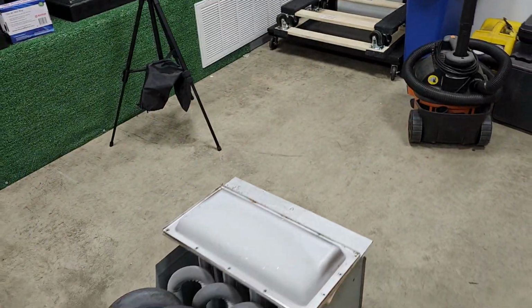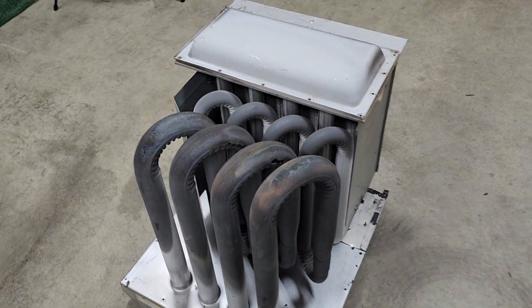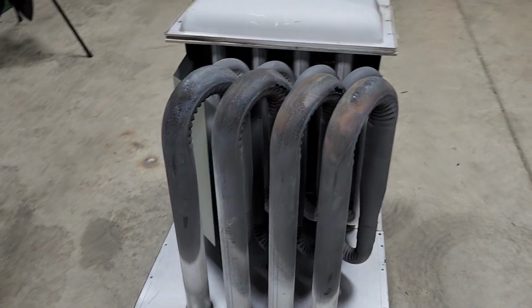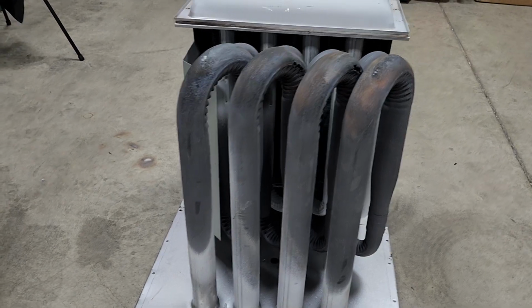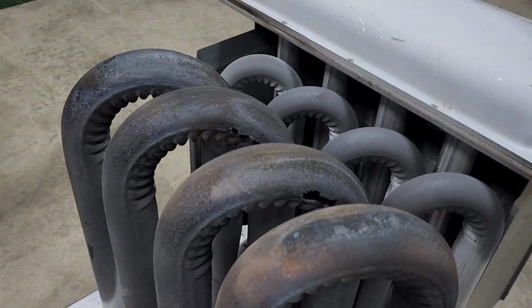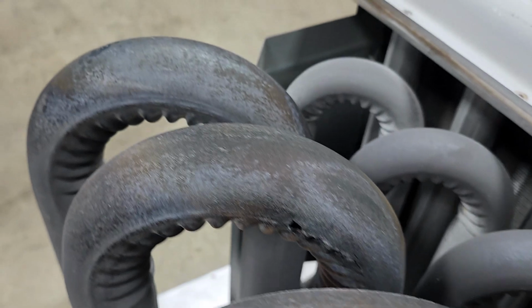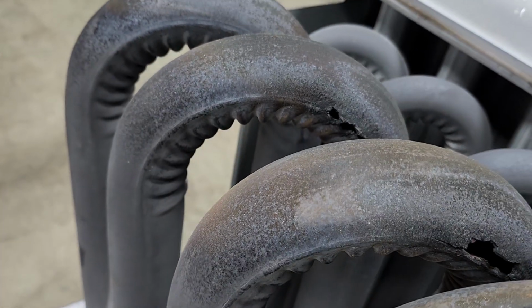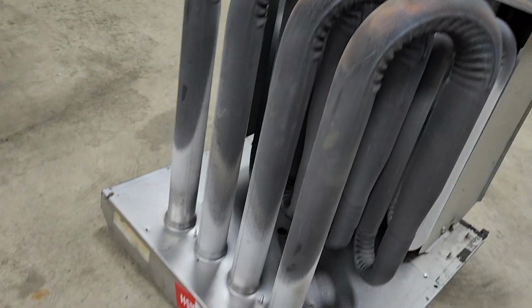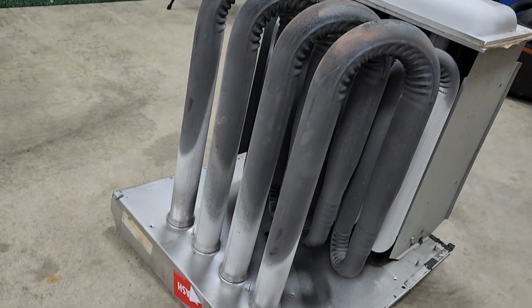I want to talk to you guys a little bit about heat exchanger failure, or preventative heat exchanger failure, real quick if you've got a couple of minutes. Here I want to show you a couple of examples of failed heat exchangers and what we can do to possibly eliminate this. As you can see here, this heat exchanger actually blew a couple of holes in a couple of the cells there. And you can tell by the coloring of that heat exchanger that this thing got really hot.